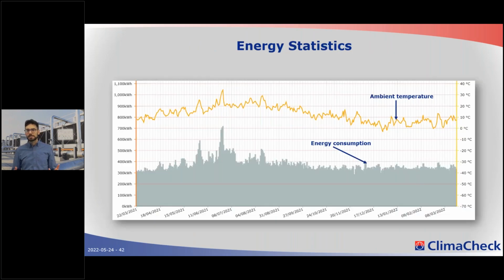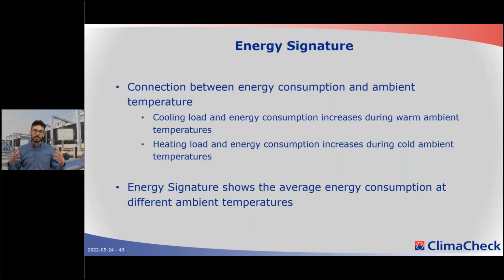Now we have the energy statistics—a long measurement representing energy consumption over the whole year. We look at how much our system is using and compare it to ambient temperature. There's a connection between ambient temperature and energy consumption: as temperature rises and we get warmer weather, there's a higher load—this is a supermarket system—so there's higher load in the supermarket system, and the rack performs worse. That's normal, and it creates a connection between ambient temperature and energy consumption.